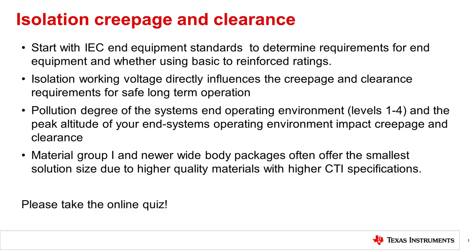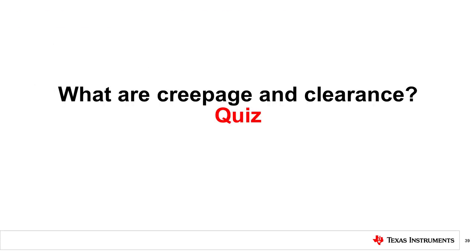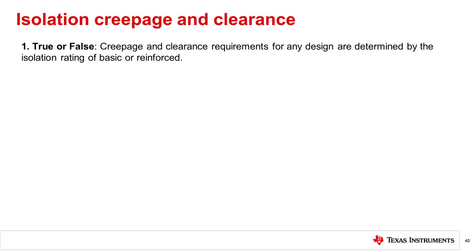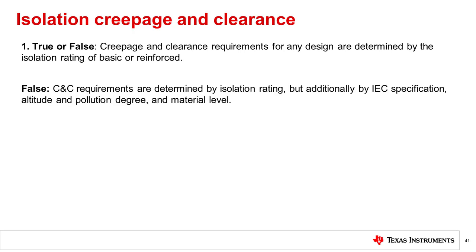Please continue watching to take the online quiz. Question 1: True or false — creepage and clearance requirements for any design are determined by the isolation rating of basic or reinforced. Answer: False. Creepage and clearance requirements are determined by isolation rating, but additionally by IEC specification, altitude and pollution degree, and material levels.